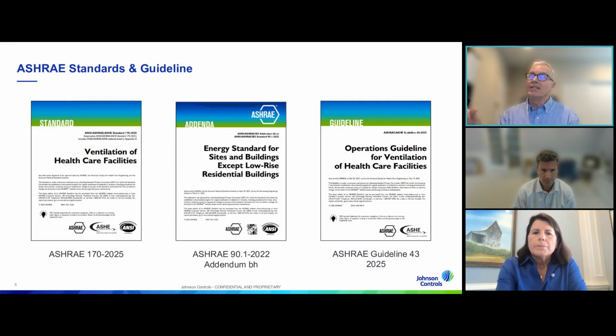now 90.1 has adopted that and put in some tighter language around it, saying that you shall now start to scale back and have those setbacks within those spaces. And it has some other caveats: you can designate a certain amount of those spaces as 24/7, continuously operating. You can have resets so that you can go back into an operational mode, things like that. But they're very specific that these areas need to be set back. And we know the reason behind that is that they consume so much energy.